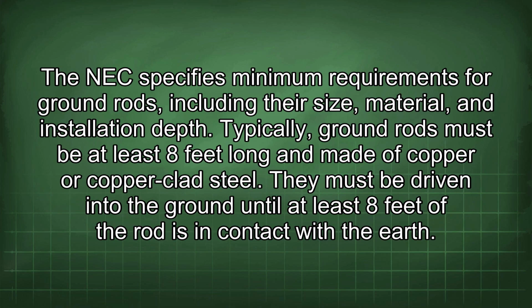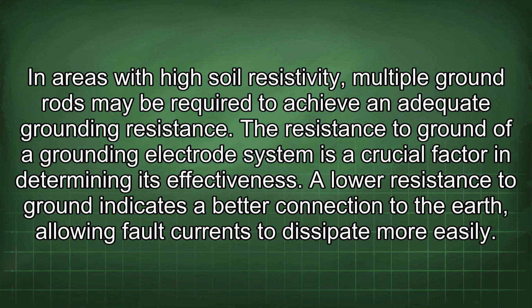The NEC specifies minimum requirements for ground rods, including their size, material, and installation depth. Typically, ground rods must be at least 8 feet long and made of copper or copper-clad steel. They must be driven into the ground until at least 8 feet of the rod is in contact with the earth. In areas with high soil resistivity, multiple ground rods may be required to achieve an adequate grounding resistance.